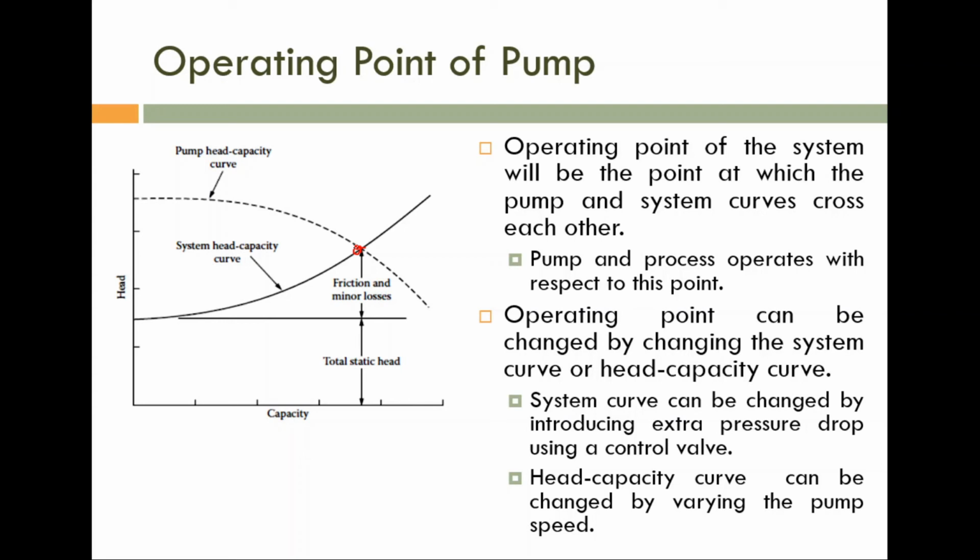So the question is, can we change the operating point? Definitely we can change the operating point. In order to change the operating point, either we have to change the system curve or we have to change the pump curve. So please note, in order to change the operating point, either we have to change the system curve or we have to change the pump curve.